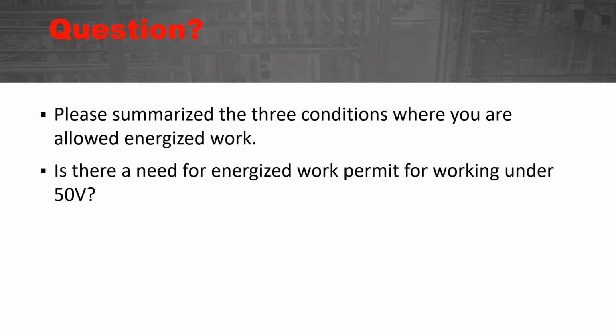In section 130.2A, 1 and 2, there are plenty of examples of additional hazards. It would be like if you're working in a healthcare facility like a hospital, where if you go to an electrical equipment room and have to turn off the whole panel, you may be turning off life support equipment. Infeasibility, an example, and it has more examples there: if you're troubleshooting, you might need that equipment energized in order to do your troubleshooting, and so that would be allowed. And then the third one, equipment operating at less than 50 volts.